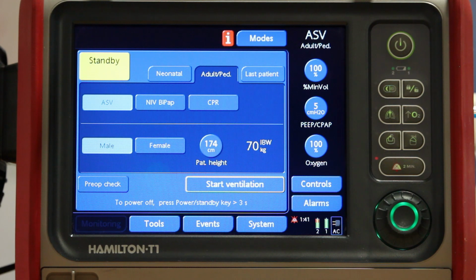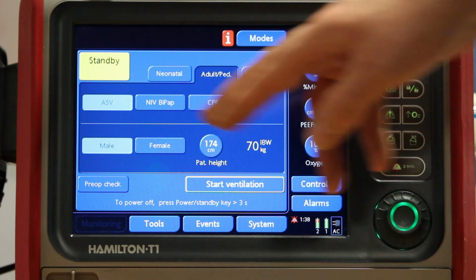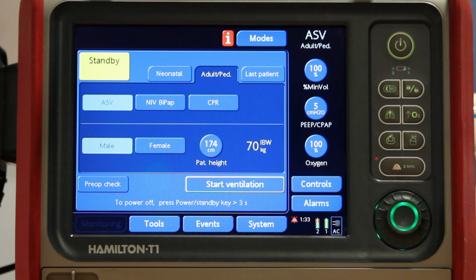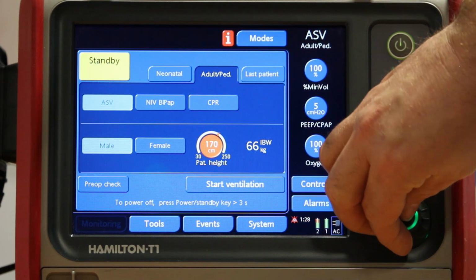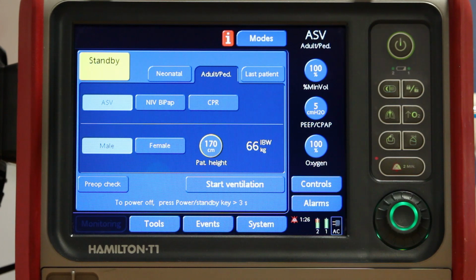So there are 3 shortcuts on the front. So if there's 3 modes that you use a lot, you can put them on the front screen. And then again, the ventilator is looking for male or female, and then it's looking for a patient height. Every height has an ideal body weight. So if we put in my own height here, you can see my ideal body weight is 66 kilos. So then we know that my minute volume is 6.6 litres a minute. So by putting in the height, the ventilator sets up defaults for delivered tidal volume, and also defaults for the alarms, the high and low limits on the alarms. Then we've got my start ventilator button.